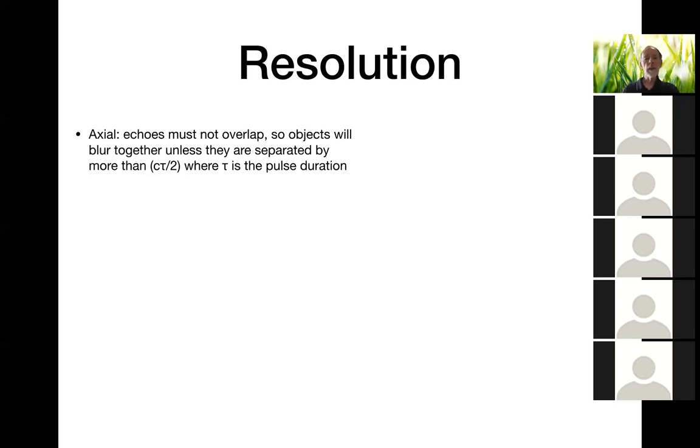We're going to see shortly that that's a lot better than the other aspects of ultrasound resolution. So the lesson from this is that the resolution of ultrasound in depth is much better than in any other direction. And this is yet another reason why you often need to try to scan tissue interfaces at 90 degrees, at perpendicular incidence, to get the greatest clarity. Of course, the machine needs to make the transmit pulse as short as possible to maximize this resolution, and it is designed to do just that.